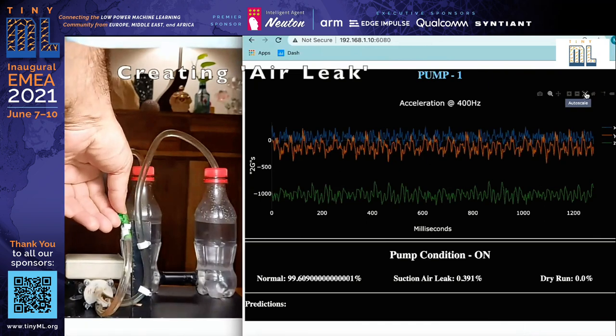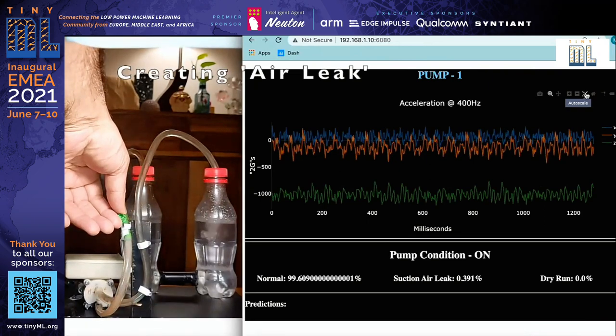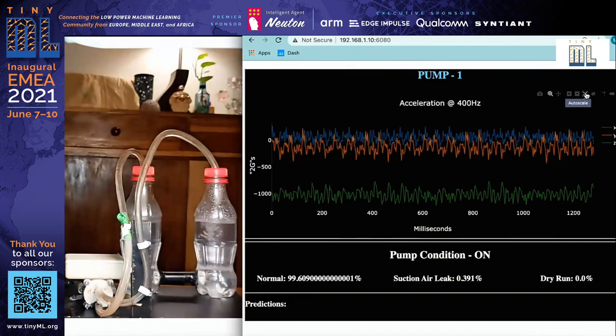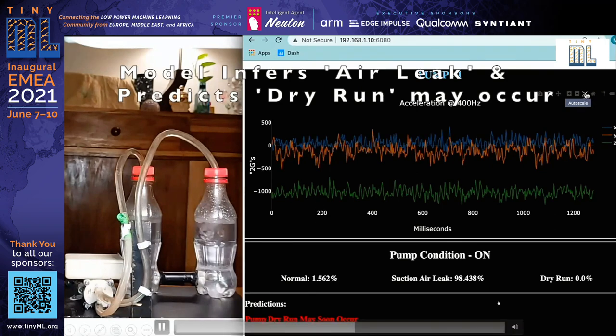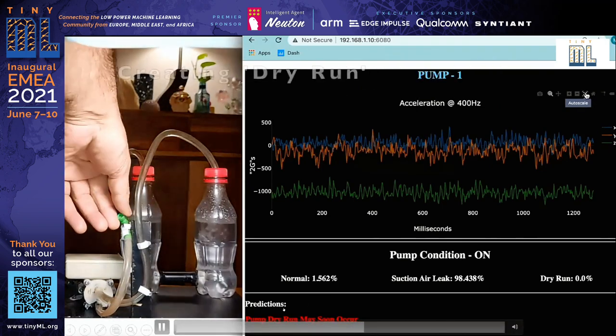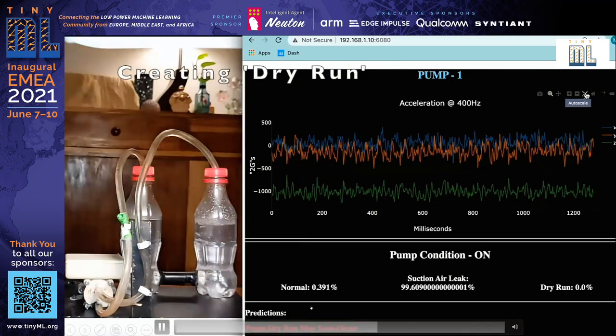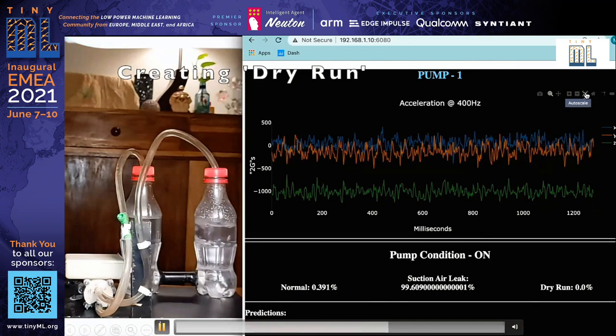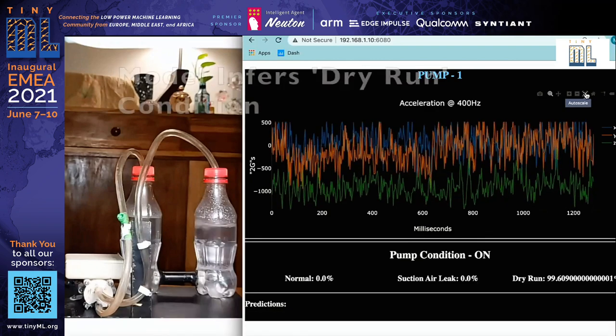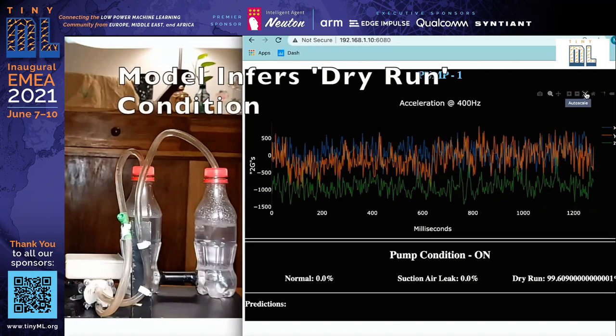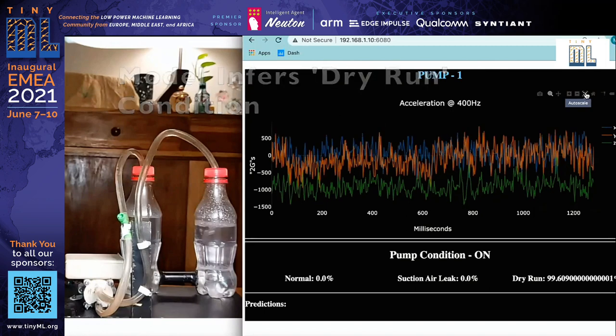We then open the air valve slightly to have some air leak into the inlet pipes of the pump. With that leak created, the air leak prediction shows 98.438%, and it's also predicting that there's a pump dry run which may occur soon. We then move on to actually creating a dry run by opening the valve further, and we see that there's a dry run that's been created.